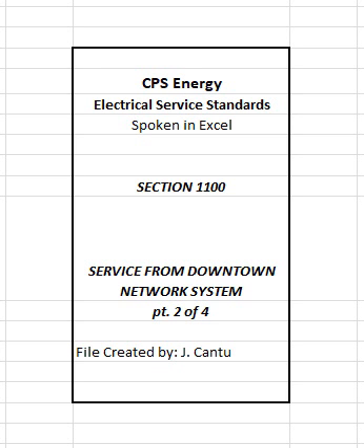Customer shall request a CPS Energy inspection a minimum of 2 days prior to each inspection. To schedule an inspection, customer may contact the CPS Energy customer service representative or refer to helpful numbers listed on the inside front cover page. Note 1. Before concrete is poured, the following inspections for transformer vaults or rooms are required: 1. Ceiling. 2. Floors. 3. Walls. 4. Doors. 5. Slab opening. 6. Vent pipe and connect. 7. Vent grates. 8. Duct bank trench. 9. Final inspection to transformer vault or room.